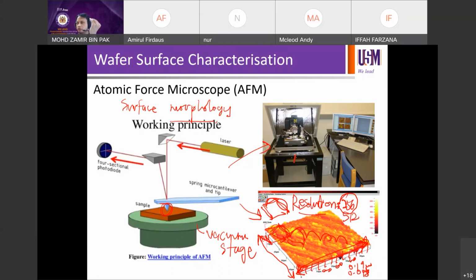In the first case, if you use the resolution of 256, you will only get information every 0.19 micron. Here to here, 0.19 micrometer. It means if you use your AFM to scan using the tip, you will get the information at this point, but nothing in between. On the other hand, if you use 512, you get the first point, and then 0.09 in between first. Then only you get the next point.